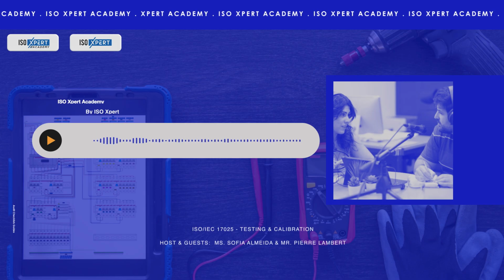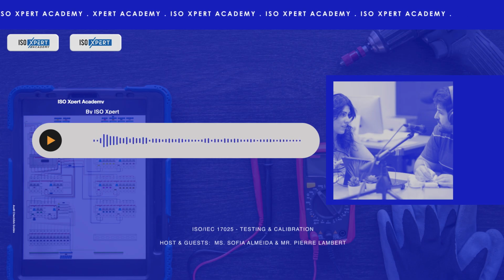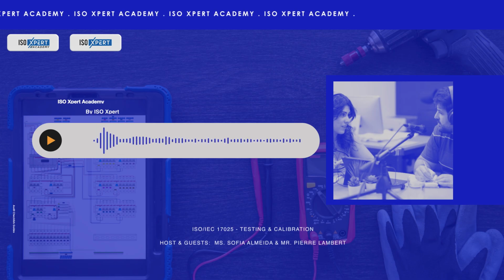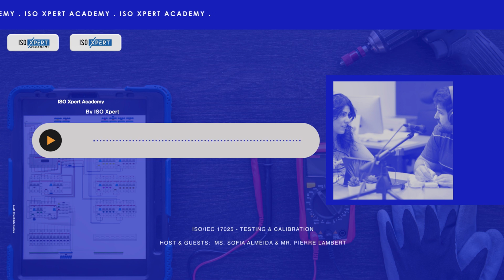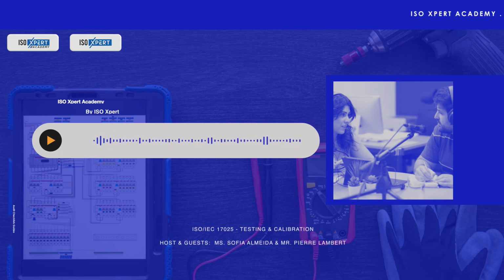And externally? That often involves participating in proficiency testing or PT programs, sometimes called inter-laboratory comparisons. How does that work? The lab gets unknown samples from an external, independent provider. They analyze them just like regular samples and report the results back. The provider then compares the lab's results against the known value or against the results from a whole group of other participating labs. Like a blind test. Pretty much. It's a true litmus test of their ongoing accuracy and their comparability to other competent labs.